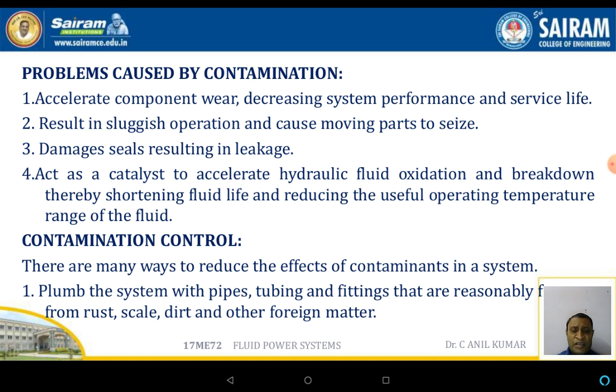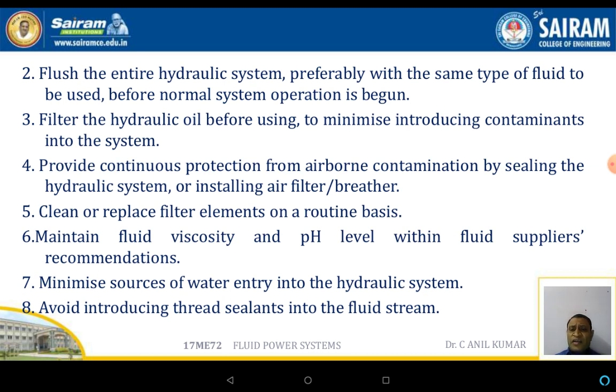For contamination control, there are many ways to reduce its effect. Plumb the system with pipes, tubings, and fittings that are free from rust, scale, dirt, and other foreign matter. Flush the entire hydraulic system, preferably with the same type of fluid to be used, before normal system operation begins. This is similar to flushing chemical laboratory equipment before use. Hydraulic oils should also be filtered before use to minimize introducing contaminants into the system.